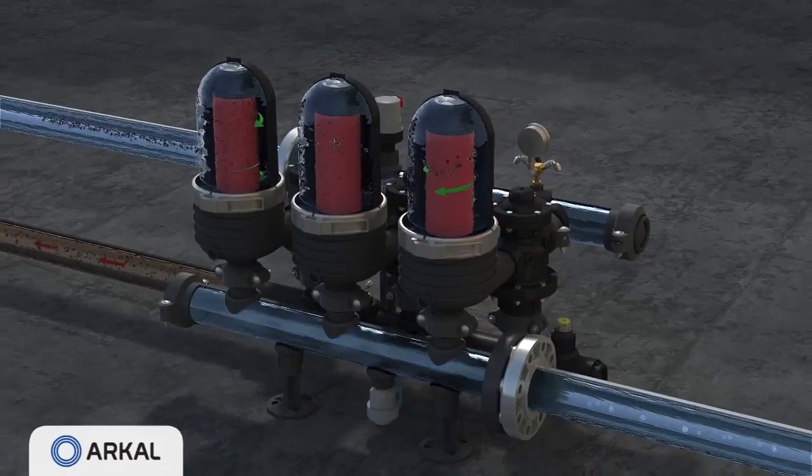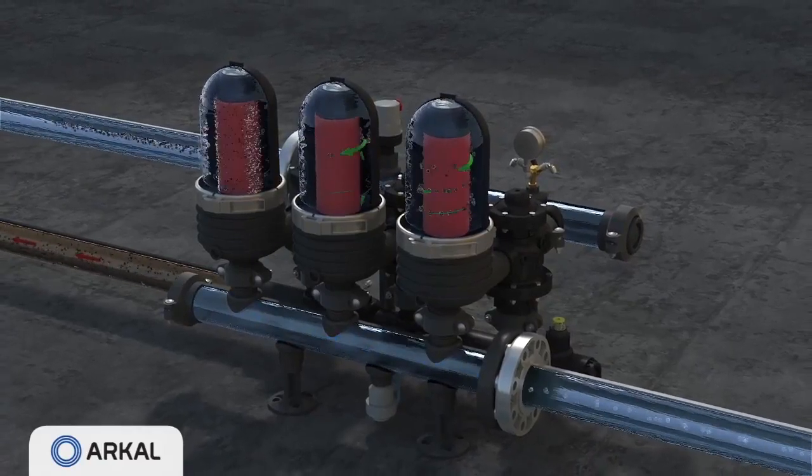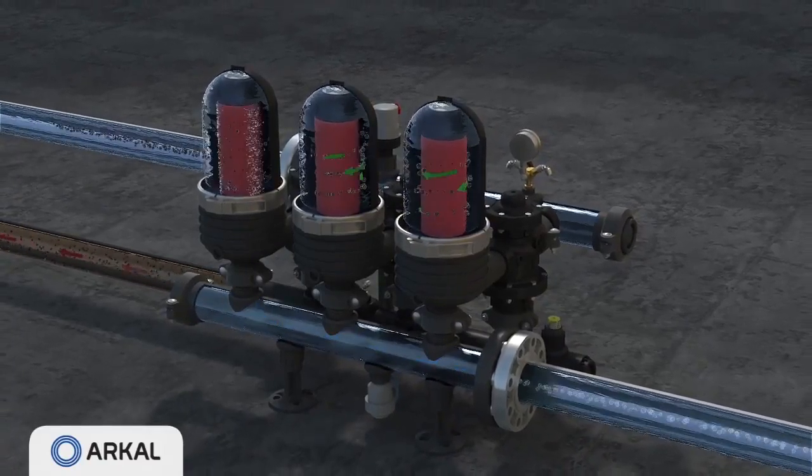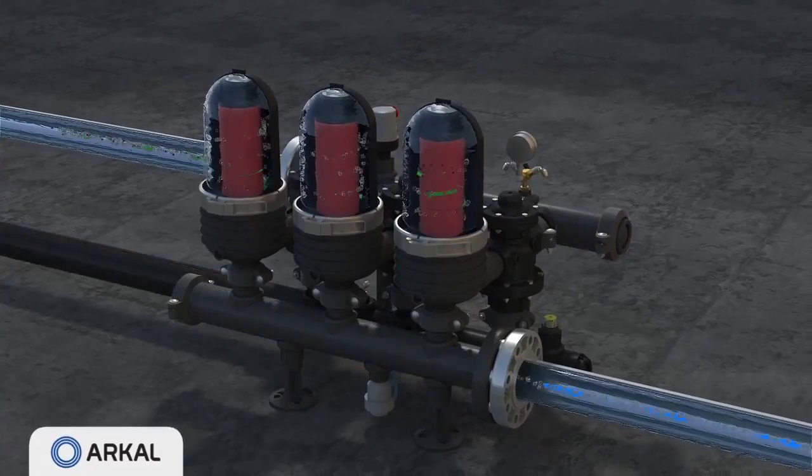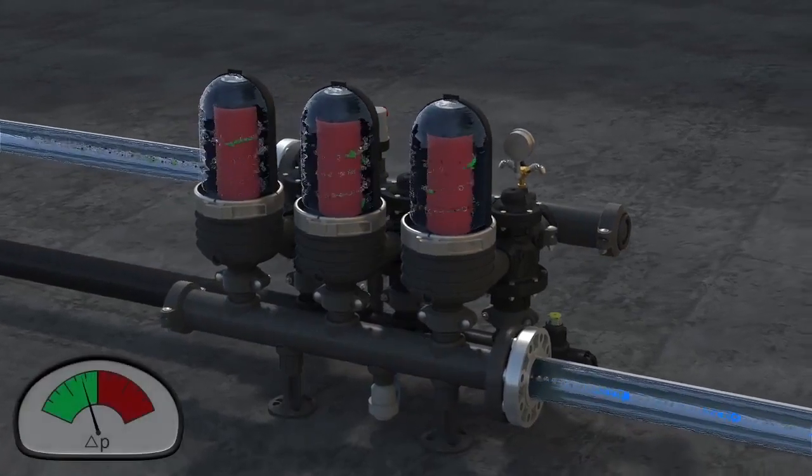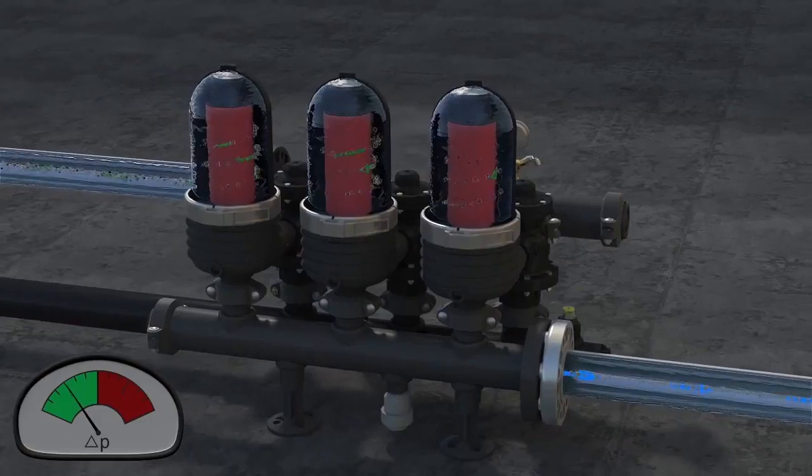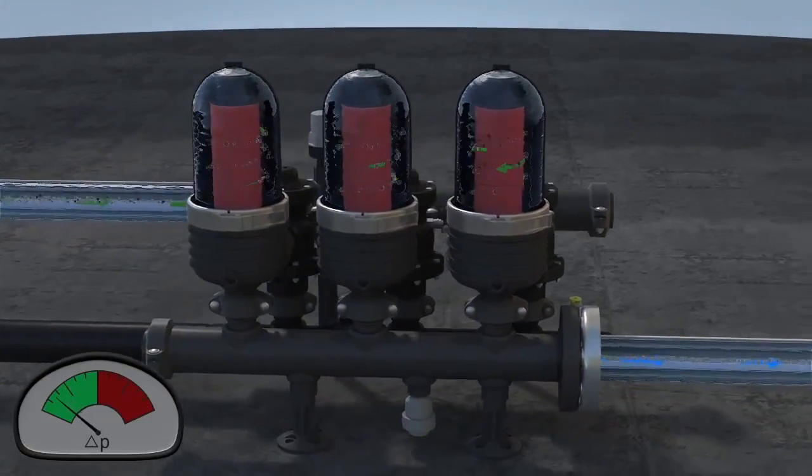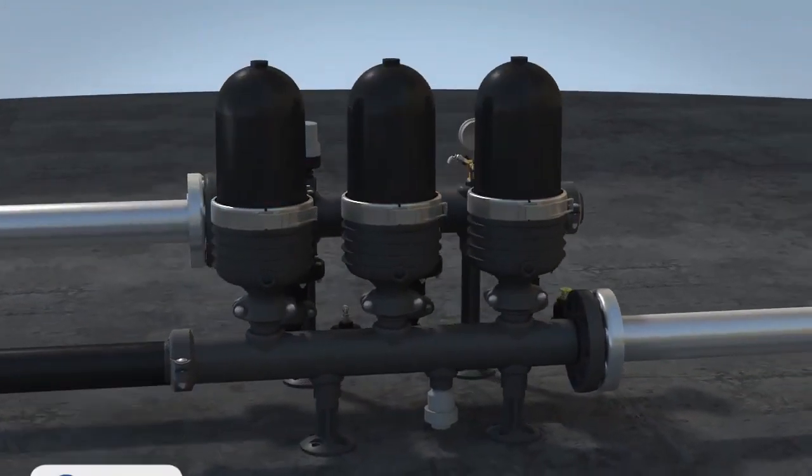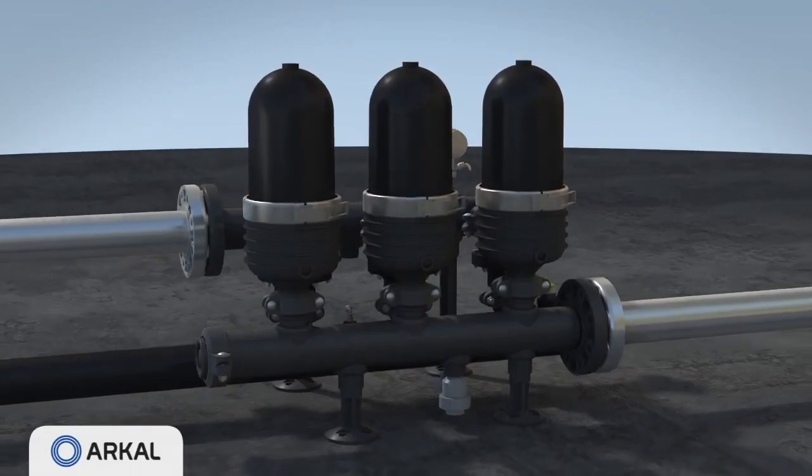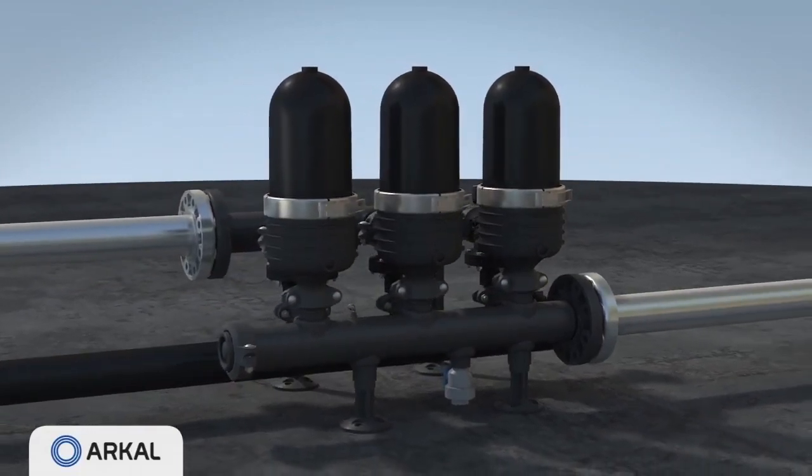At the end of its allotted cleaning time, the flushing module returns to filtration mode and the next consecutive module starts cleaning. This process continues till the last module is clean and the PD switch returns to its green zone. The system returns to filtration mode until the next flushing cycle is triggered.